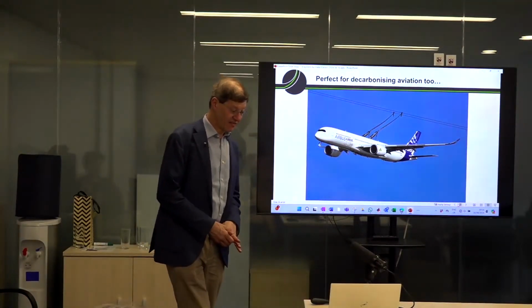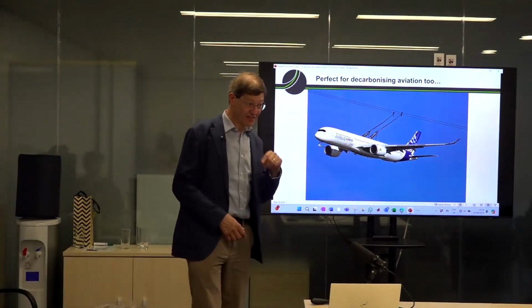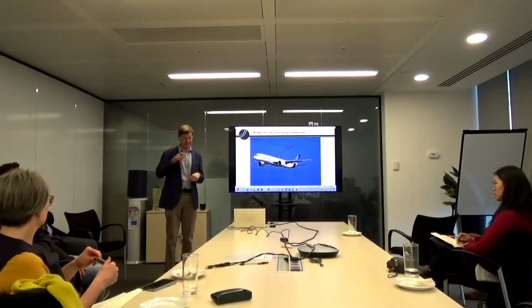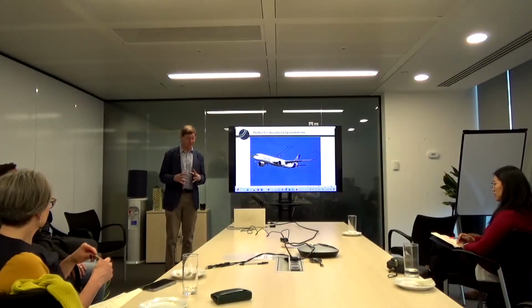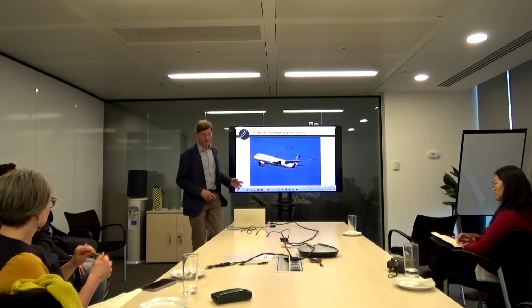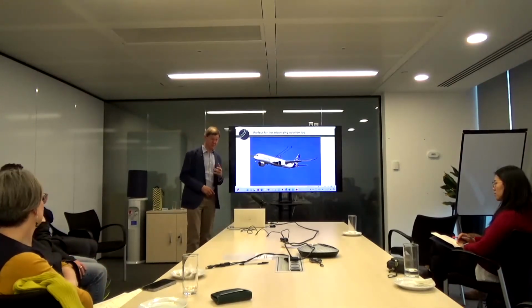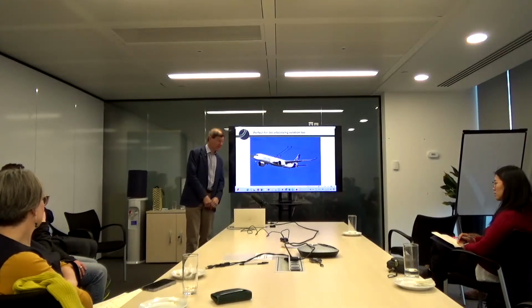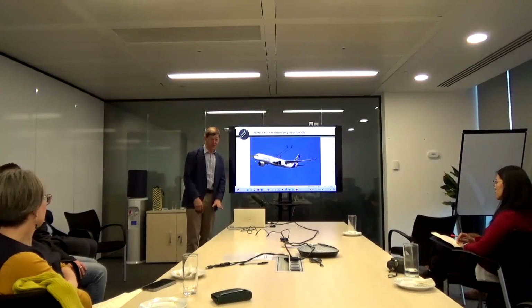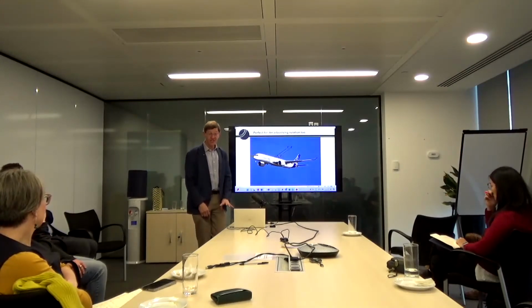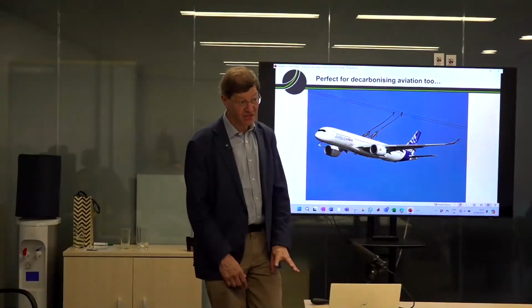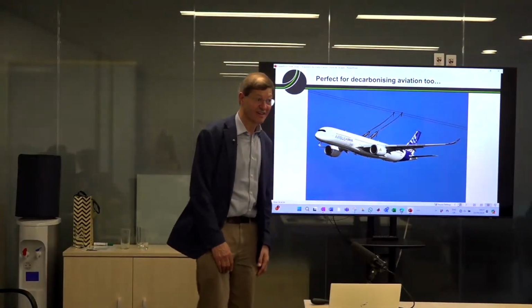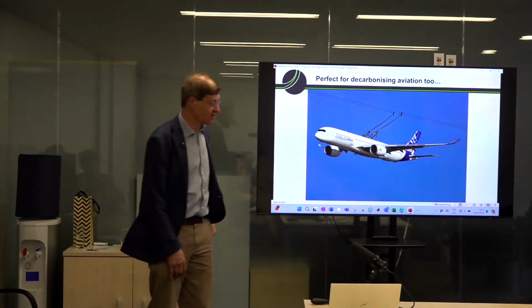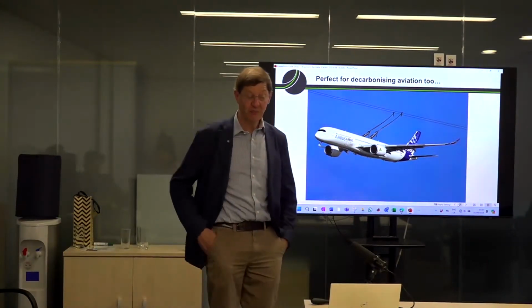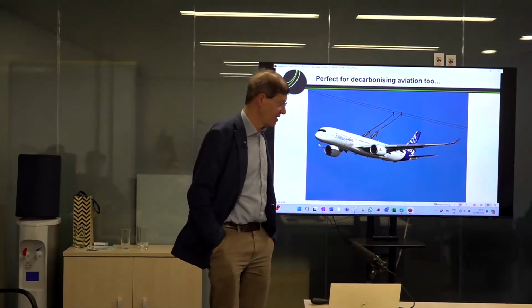With hydrogen, because its calorific value is a third of methane's, you have to pump three times more of it, boosting the pressure. But because of embrittlement issues, you have to pump it at a third of the pressure. So your gas pipeline's capacity ends up being about a tenth, a third of a third. The idea of using existing gas pipes is completely crazy - you'd need ten times the amount if you used the same current materials.